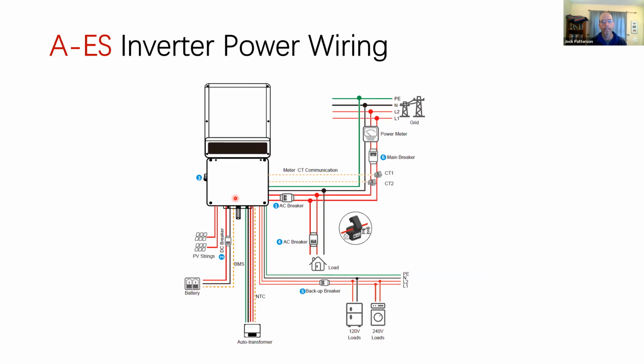We need to be able to say, for safety reasons, turn your voltage on. I mean, this is potentially a 400 or 500 volt battery. These are allowed at residences because of these controls. That's when the NEC makes an exception. It'll allow you to have over a 100 volt battery because you have a smart battery. That's why our batteries have these communication lines. They have to be smart, and therefore they're safe.